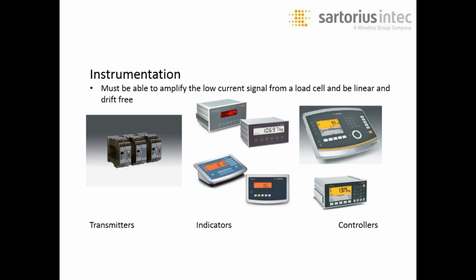Instrumentation comes in many forms from many different manufacturers. The three most common formats are transmitters, indicators, and controllers. The transmitter does exactly what it says. It takes the weight data and transmits it out on a customer-selected field bus. That could be Modbus, Ethernet TCP/IP, EtherNet/IP, DeviceNet, Profibus, or simply RS-232.